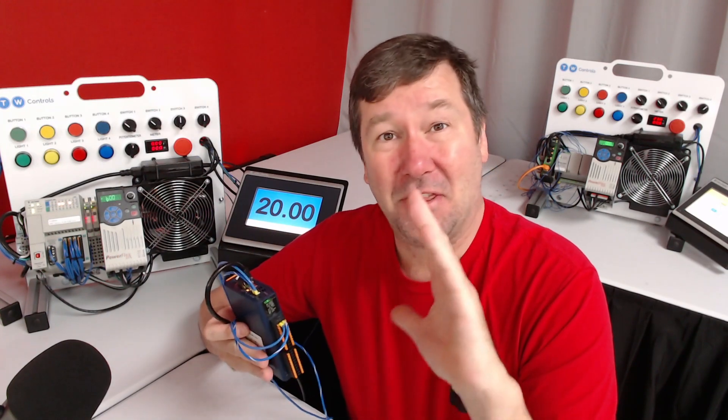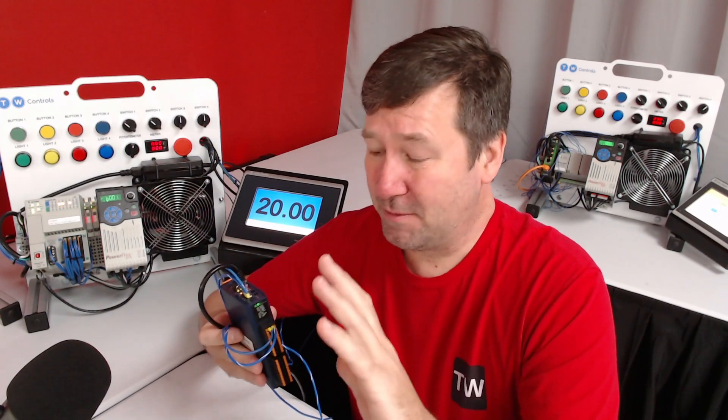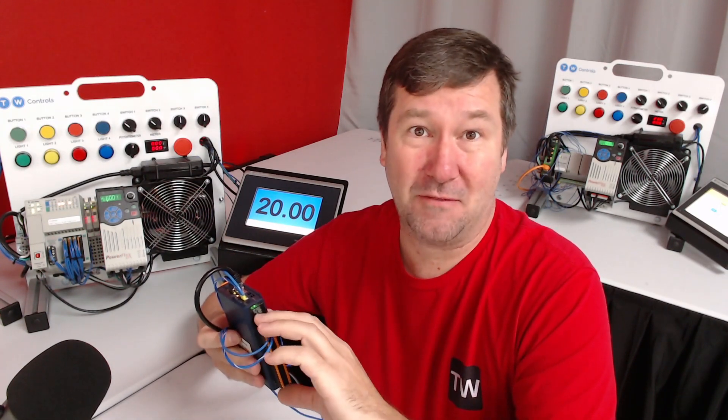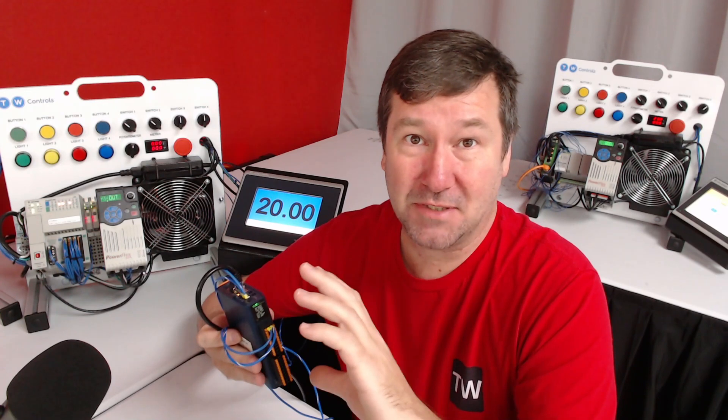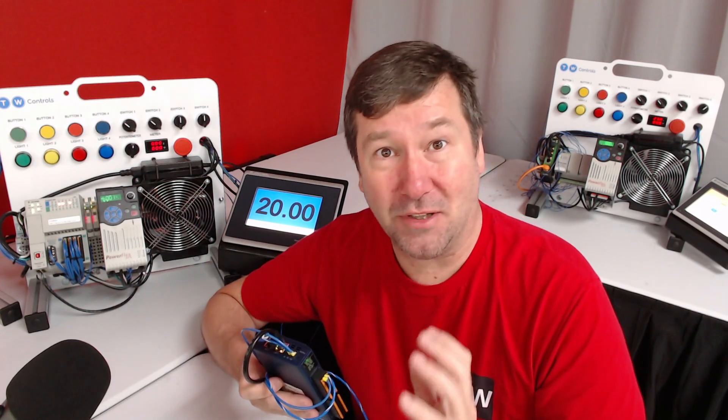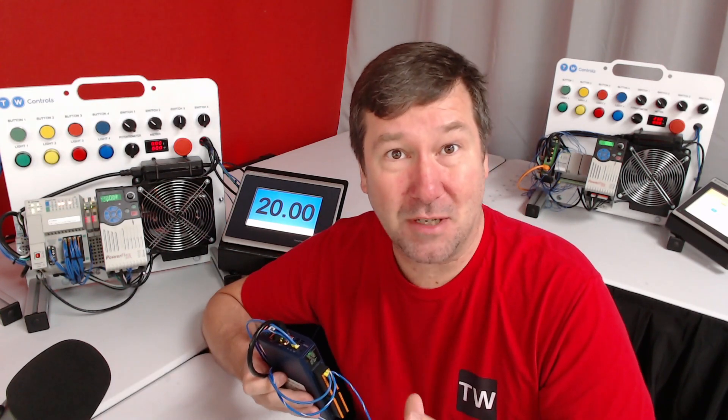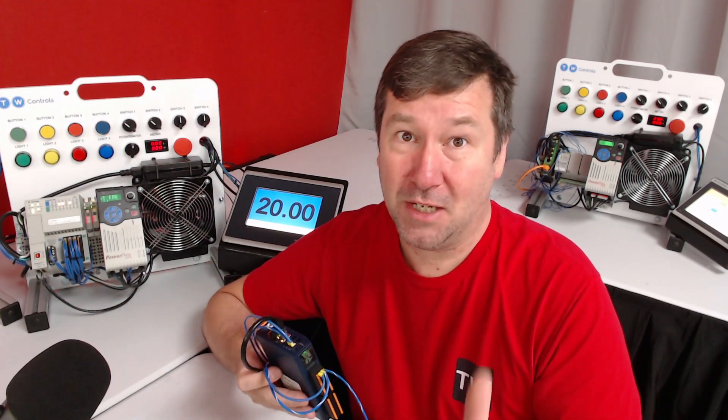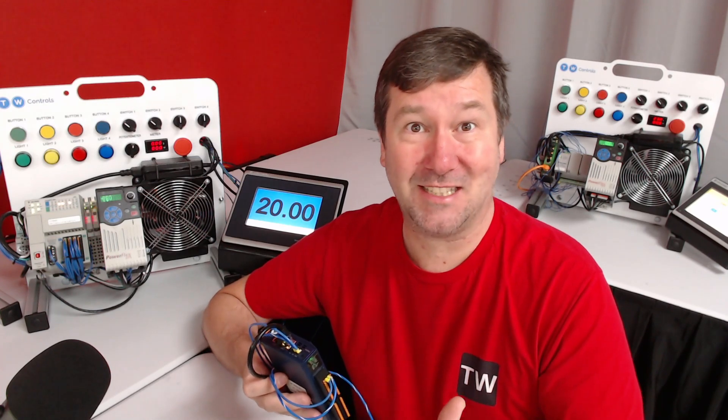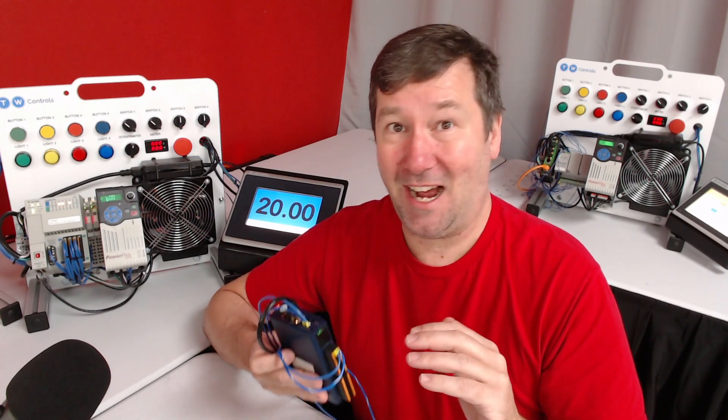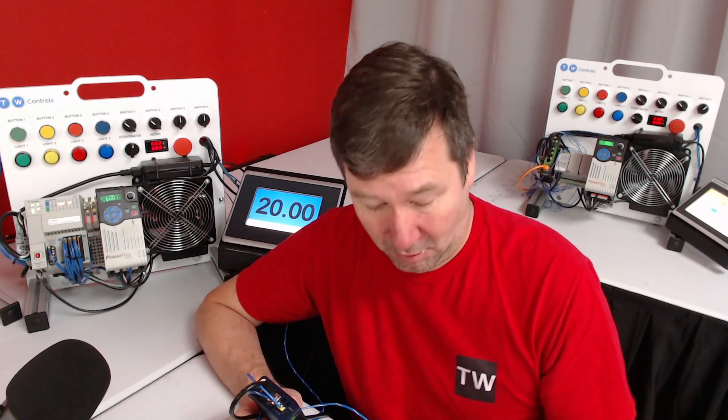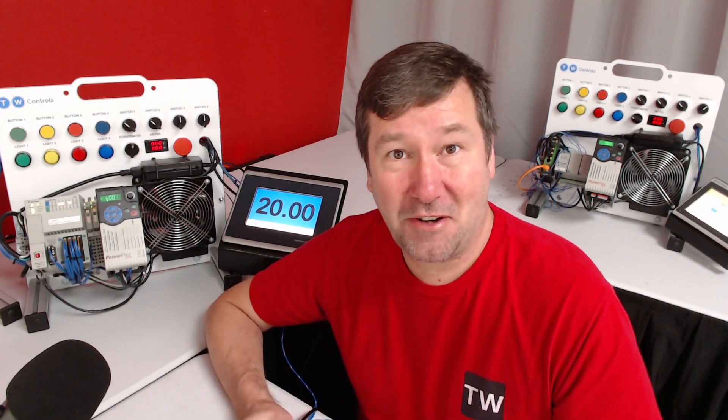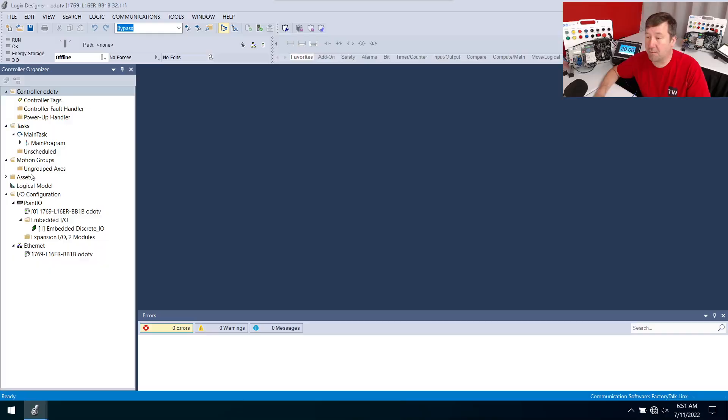They have an EDS file that makes it super simple to drop it into the configuration of Studio 5000 and most importantly gives you the 4 to 20 milliamp value of your analog signal. This is something that I go through every day with people on our analog simulator - how to measure a 4 to 20 milliamp signal. Let's go through how to set it up.